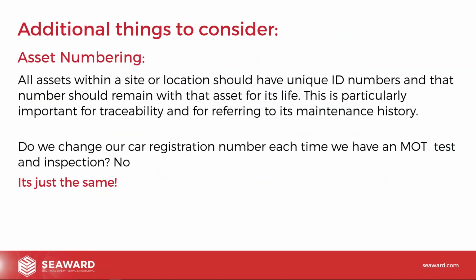So additional things to consider: asset numbering. Asset numbering is quite important, because what a lot of companies do is they'll just number everything every 12 months, so nothing ever has the same number for more than one test. The problem with that is that if you don't keep a unique number for each item going forward, you haven't got the traceability. That equipment could have gone faulty 3 times before, but you wouldn't know, because you give it a fresh number each time. So it's almost got a fresh record each time, and you're not picking up any patterns, trends or traceability. So we always recommend unique asset numbering for items, even if you're using a manual system.